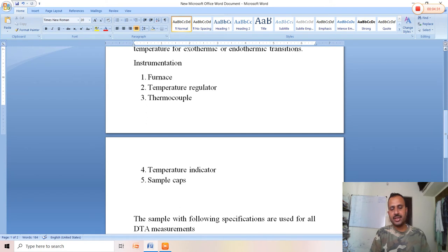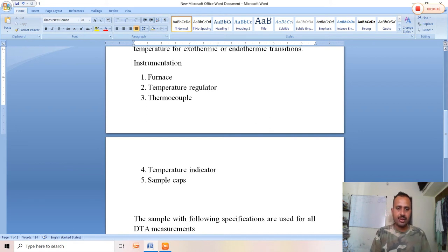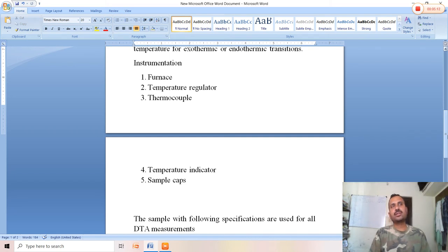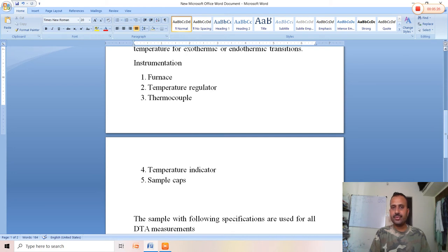The instrumentation of DTA consists of: first, a furnace; second, a temperature regulator; third, a thermocouple; fourth, a temperature indicator; and fifth, sample caps, which serve as the sample holder. The furnace provides heat and temperature for the DTA analysis. The temperature regulator provides a linear heating program. Two chromel-alumel thermocouples are used in DTA: one records the temperature of the furnace, and the second records delta T using a microammeter.